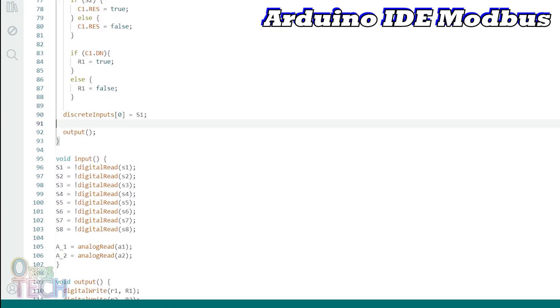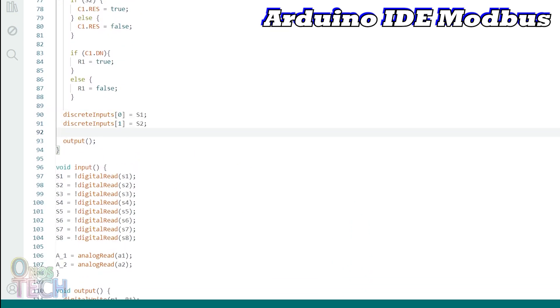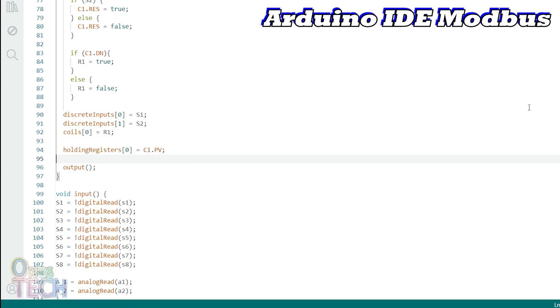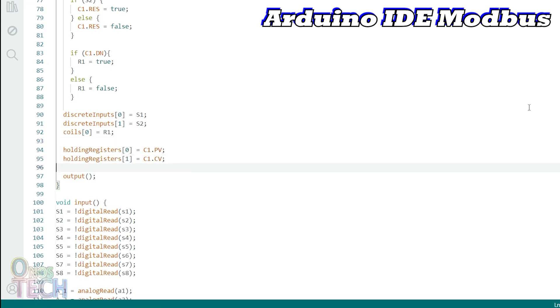Assign S1 and S2 to the discrete input array and R1 to the first element of the coils array. Also assign C1.PV and C1.CV to the holding registers array.